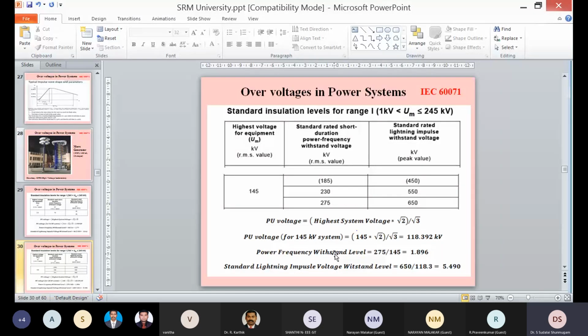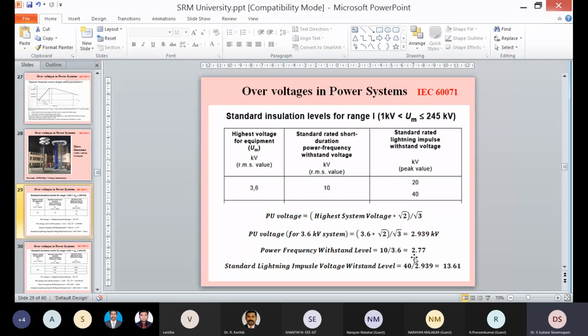So for a 145 kV system, if you substitute in the formula, per unit value is 118.392 kV. Your power frequency withstand level is 1.89 times the highest system voltage, whereas standard lightning impulse withstand level is 5.49 times higher than the per unit value. You see here, when we consider 3.6 kV, it is 13.61 times higher. However, when I move to 145 kV, it is only 5.490 times higher. That's what I told. When you move to higher and higher system voltage, your lightning impulse level as well as switching impulse level will come down, and when you move above 600 kV, both will be very close to each other. Again, the three levels which they have given depend upon the type of earthing system.